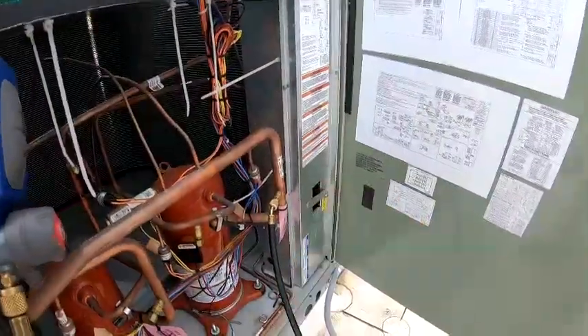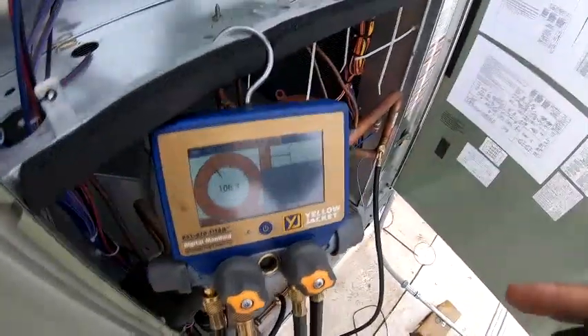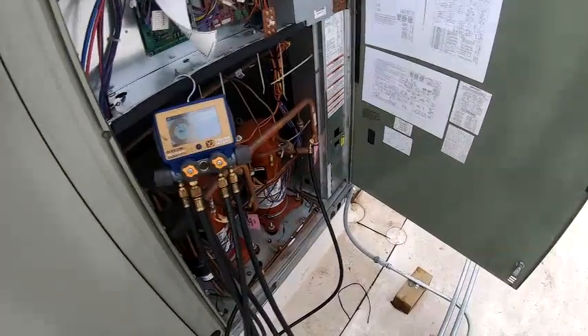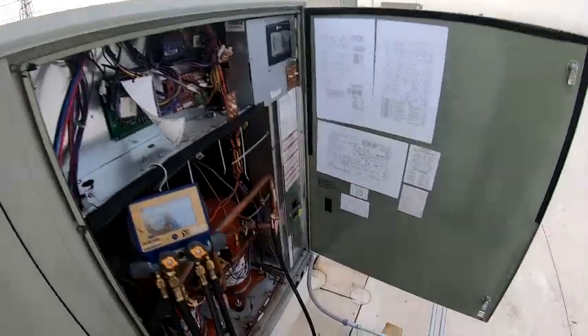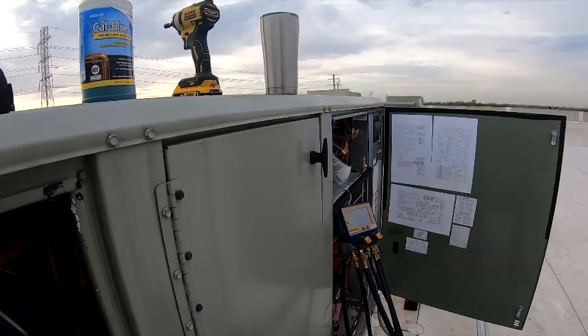And you can do soap bubbles, do a leak search, because if it doesn't drop below, I'm going to pull these gauges out and start checking these Schrader valves. Just check all the joints, make sure we don't have a leak. If the nitrogen still goes below my 106 or that 0.6%, I may have a small leak, so I can put some trace gas in there with 410A and check it with the H10 Pro electronic leak checker. If I don't find anything, or the pressure test does hold up, we can leak check it with the vacuum pump, pull it down to 500 microns, and make sure we don't have a leak there.